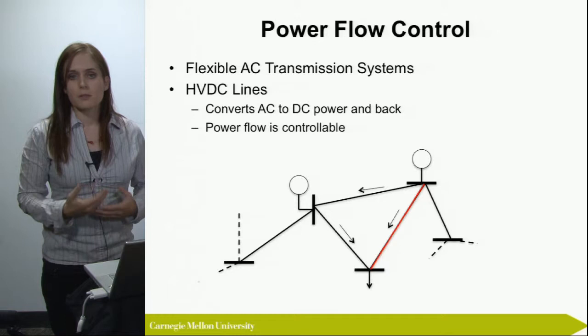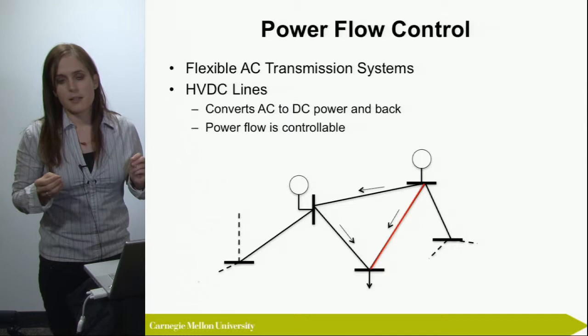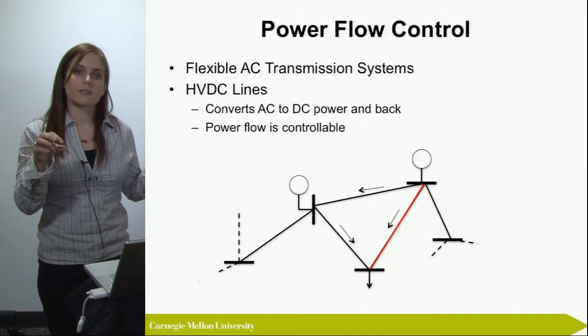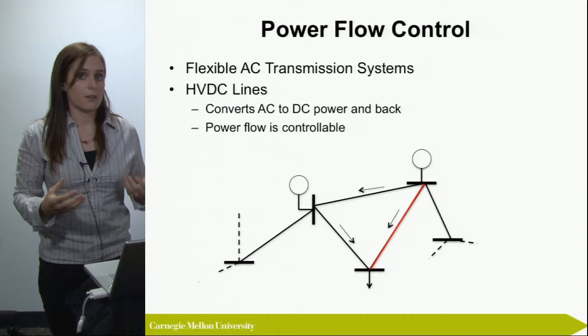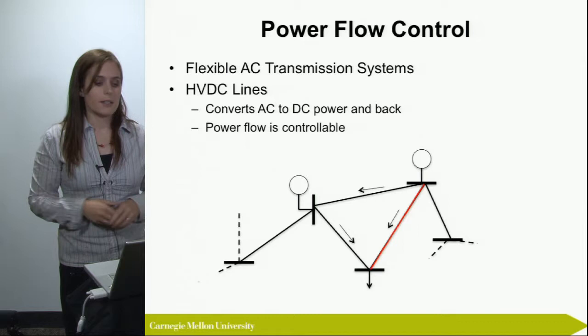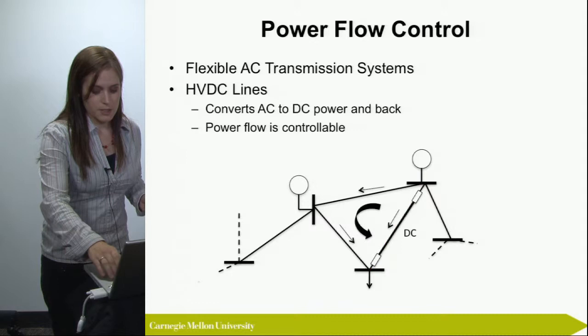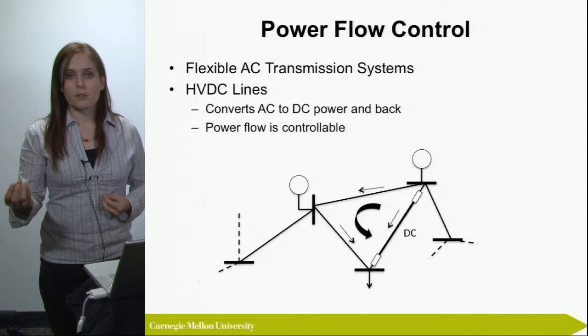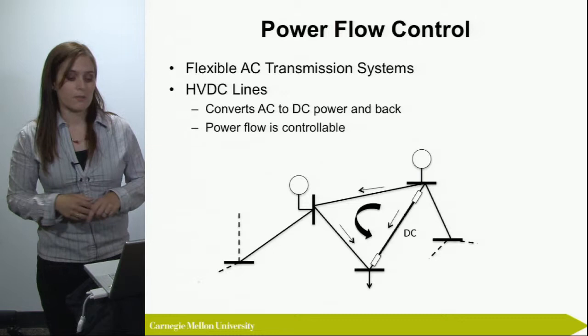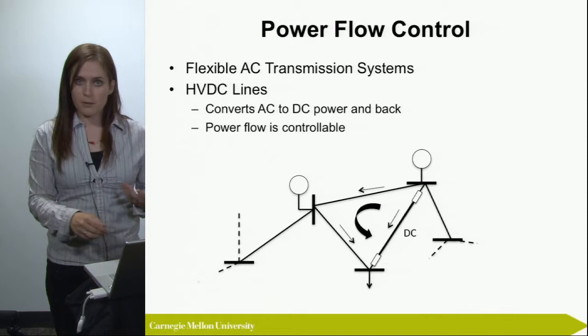Another device for influencing power flows is HVDC lines. With HVDC, you convert power at one location into DC and then convert it back to AC at the other end of the line — the traditional power system is based on AC, which is why the conversion is needed. The advantage is that you can decide how much power you want to transmit over that line. This allows you to reroute power over the rest of the system, making power flow controllable.